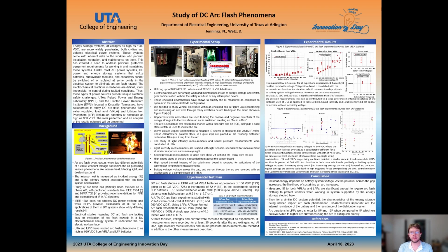An arc flash event occurs between two different potentials of a circuit that ionizes the air in between them. This ionization of the air produces a blast pressure, blinding light, deafening sound, and intense heat. This intense heat is measured in the form of incident energy and is the primary hazard associated with arc flash fatalities and injuries.